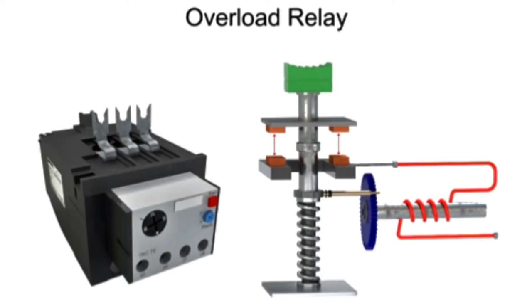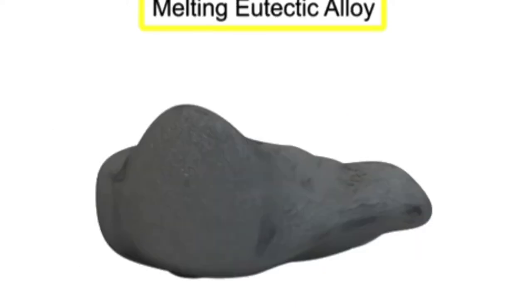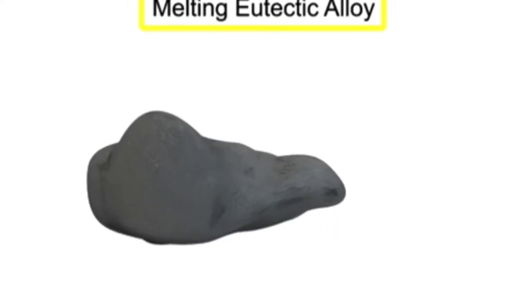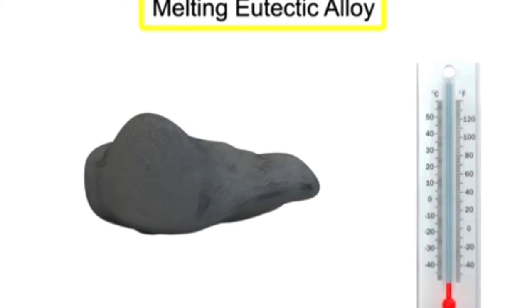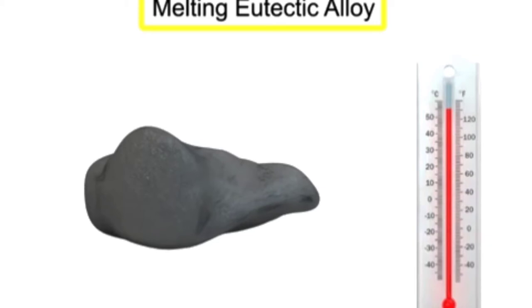The most common type of overload relay uses a melting eutectic alloy. A eutectic alloy is a specific type of metal that changes directly from a solid to a liquid at a fixed temperature.